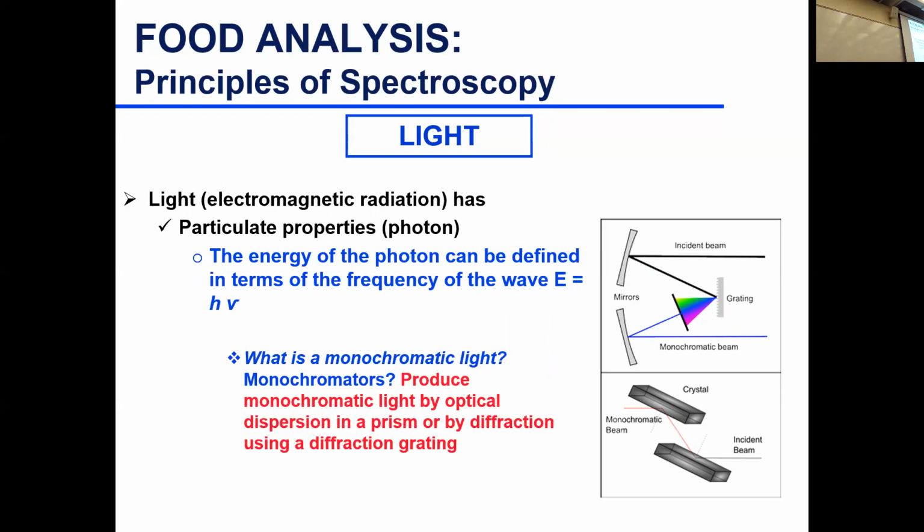So in the spectrophotometer unit, what will happen is you have your incident beam from the source of light. You have a mirror, just to make the compartment small. You have a mirror that projects the light into a grating system. The light gets diffracted. Then you have a slit that you can move. That slit can be moved and allows a singular wavelength to go through onto a mirror, and then a monochromatic beam, where you have a sample here, is projected onto the sample.